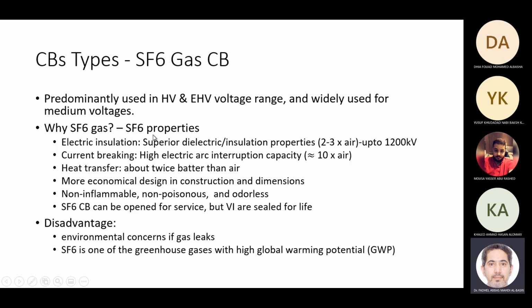SF6 is a gas. It has very superior dielectric properties, insulation properties. It is 2 to 3 times better than air. It has high breaking capacities, it has better heat transfer, and it is non-flammable, non-poisonous, and odorless. Doesn't have a smell.